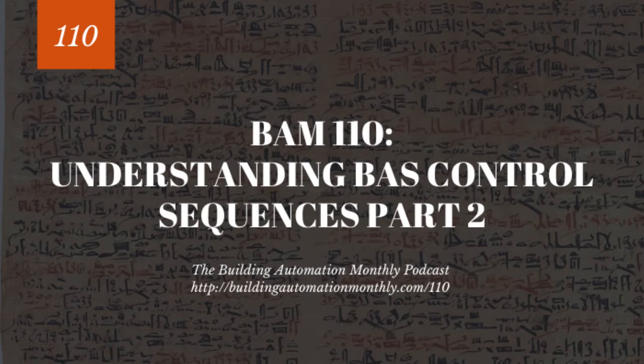Then we have the alarms, and I always say that you should focus on the alarms after the control modes and after the enable modes, because the alarms should always override everything else. What I mean by alarms is if you have a high pressure shutdown, low temperature alarm, smoke alarm, those life safety or equipment safety alarms should take priority over all the other control modes and enable modes that we're looking at in our sequence and programming.